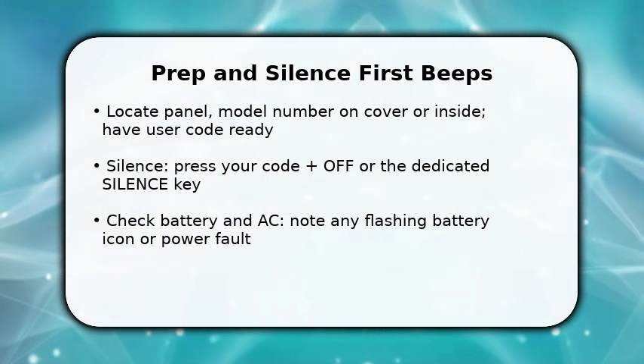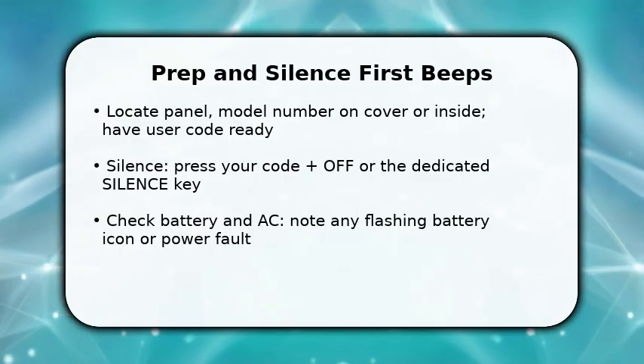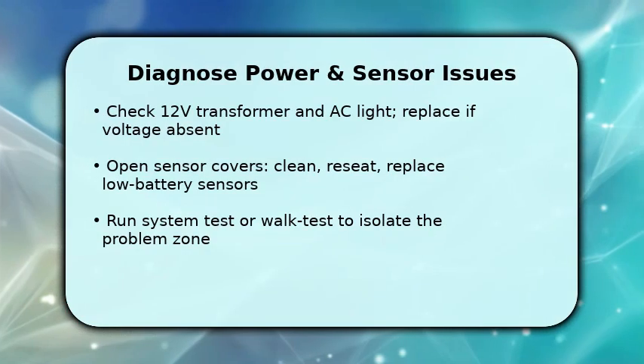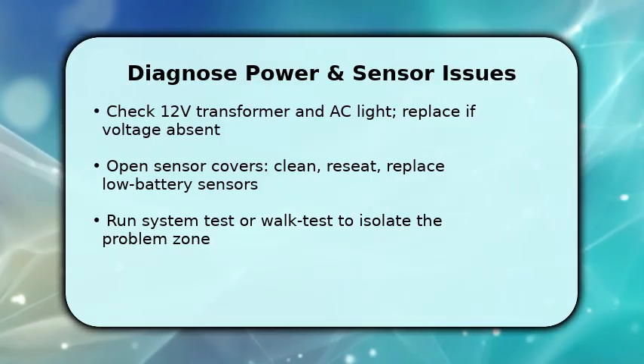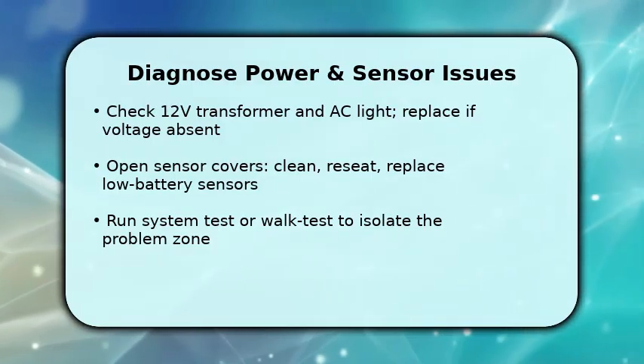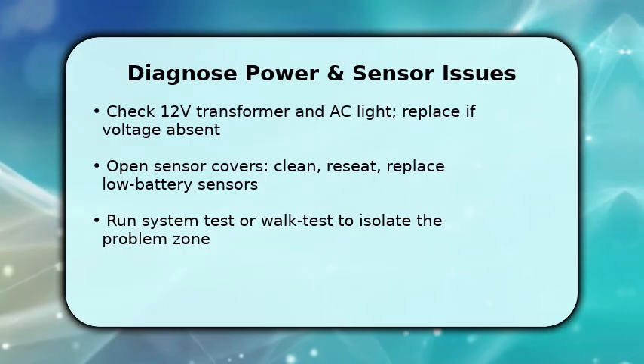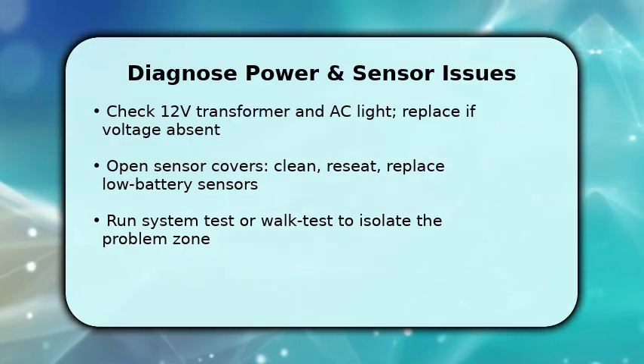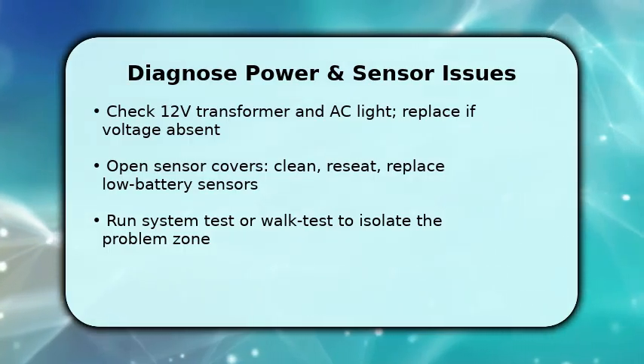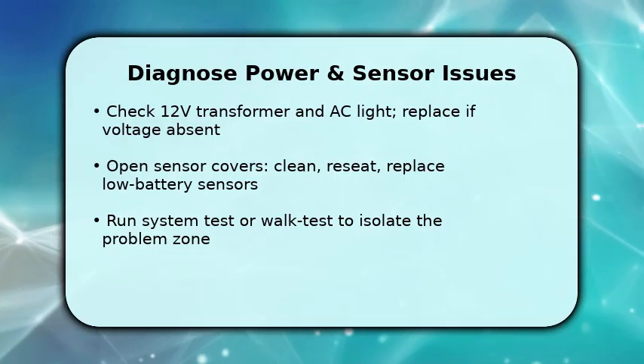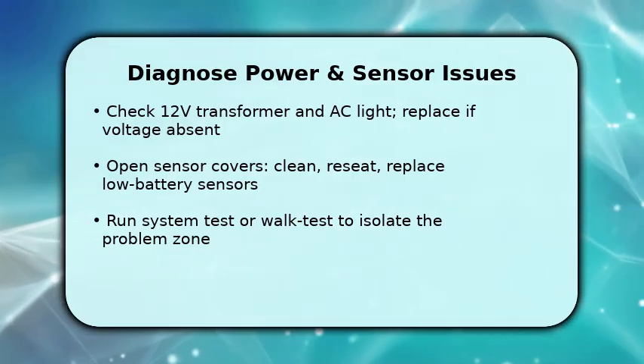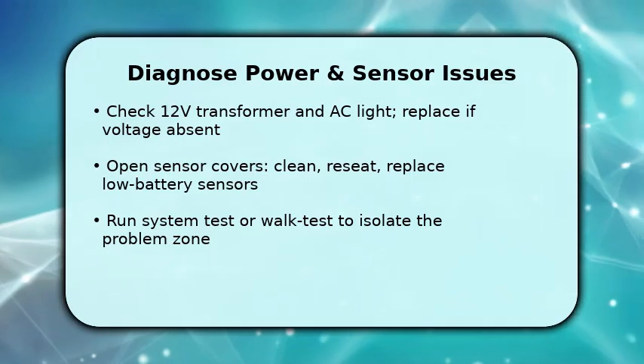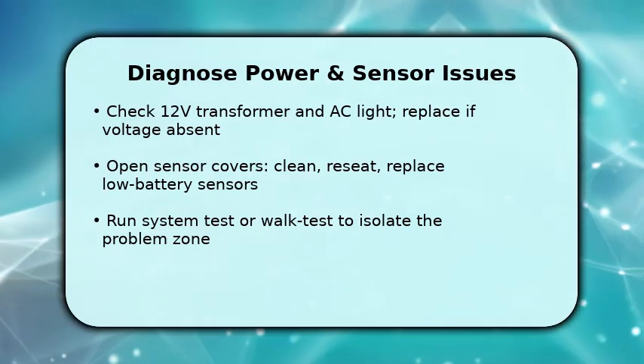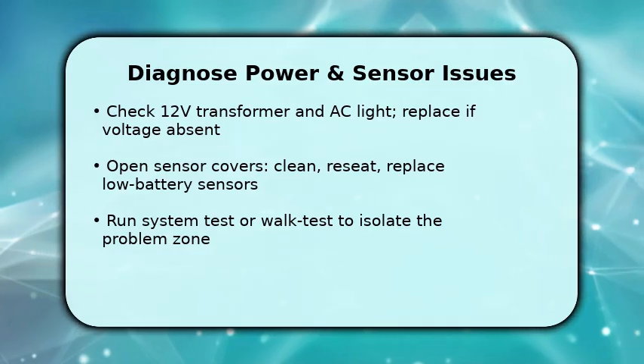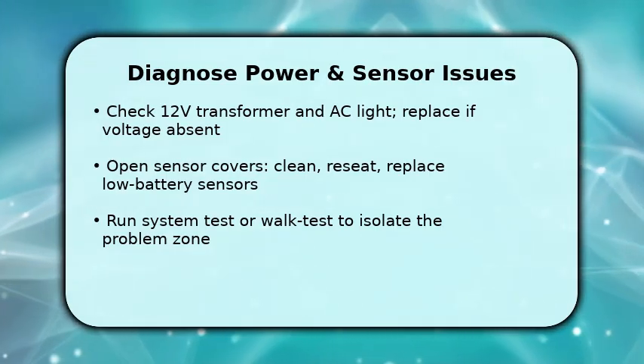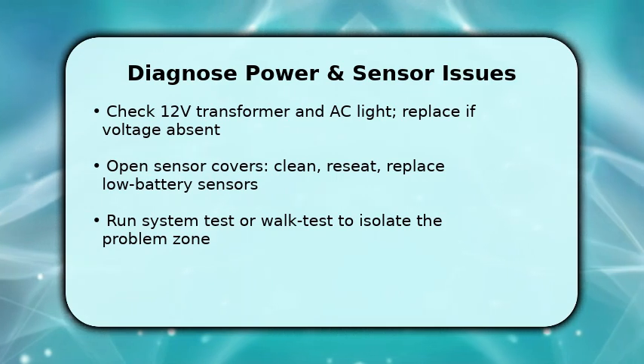Next, diagnose likely hardware causes. You check the transformer and AC indicator because loss of AC or low voltage leads to beeping. Replacing the transformer or restoring power stops those alerts. Then inspect wireless sensors. Opening covers, cleaning contacts, and reseating batteries often clears chirps caused by low cells. Once components look good, run a system or walk test to pinpoint the faulty sensor or zone. This reveals why. Finally, complete the repair with a proper reset and verification.